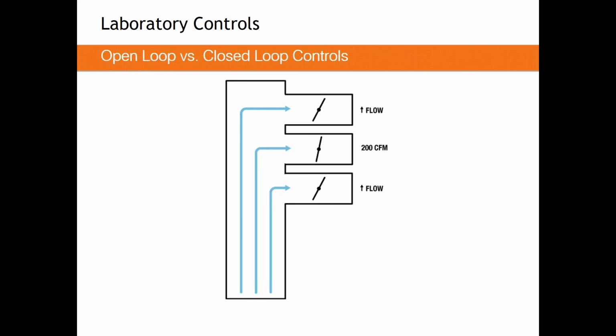So what's going to happen in this system is we're going to instantaneously increase the pressure in this system and the flow through the other 2 valves. So if you imagine fume hoods, your middle fume hood's still operating as intended, but the other 2 fume hoods instantaneously and momentarily have increased their flow rate, which is an unintended consequence. The other 2 valves will have controllers that will take care of this, and they can take care of it fairly quickly and accurately, but still for a few seconds they are not at the airflow they want to be at. And all of this occurs because pressure and airflow are directly linked together.